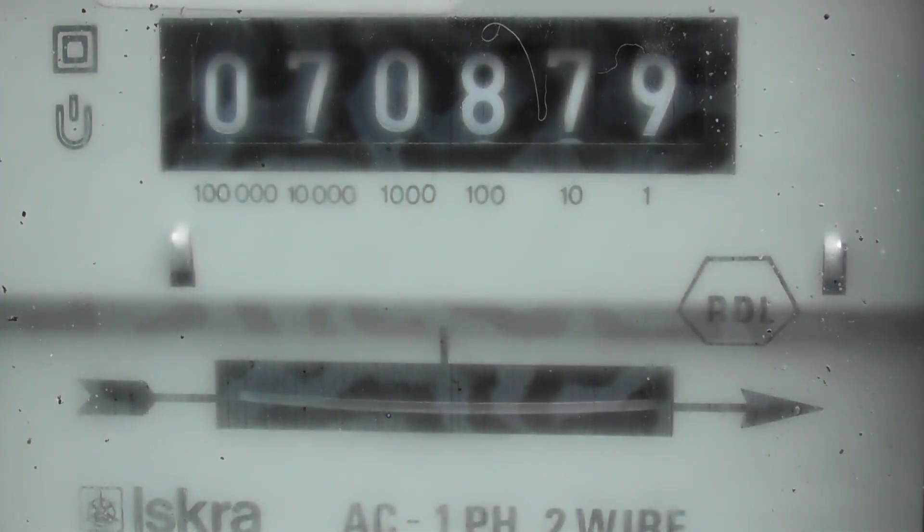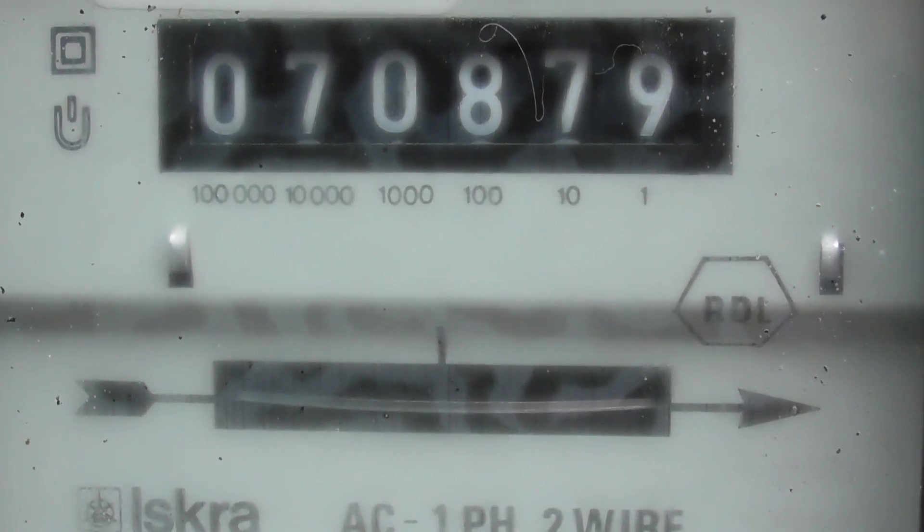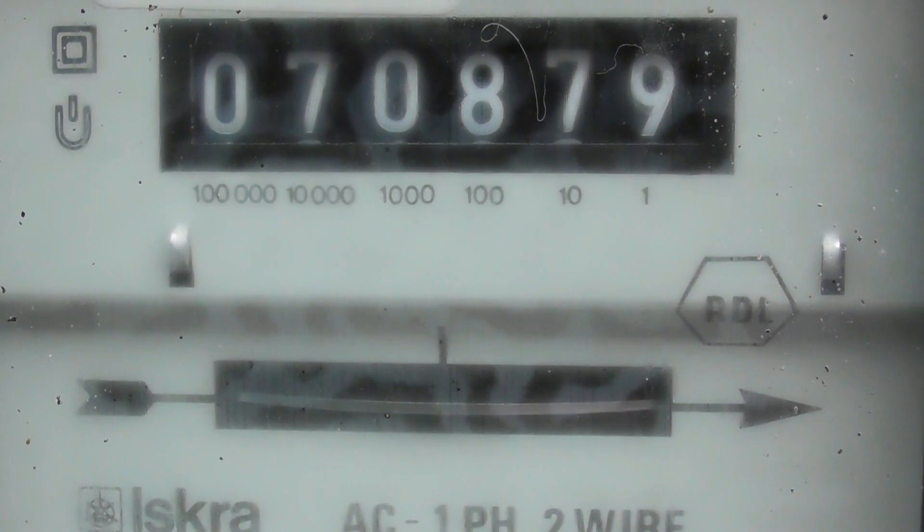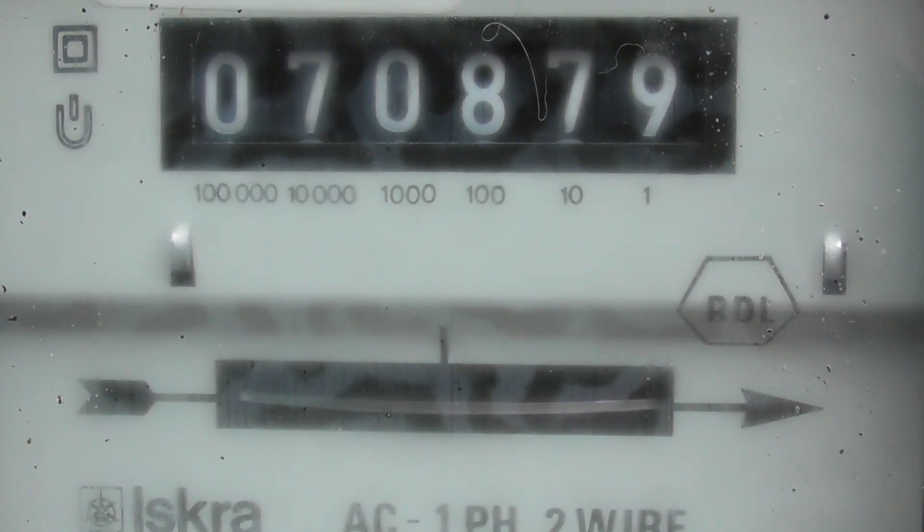Well then, the normal dial test check meter you see going forward hasn't got a reverse running stop. So I'll change the polarity. The meter will run the other way happily, so the numbers will count backwards.